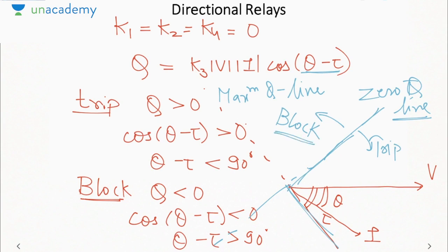Okay. So that is the phasor diagram or graphical representation of the operation of directional relay. Is it fine? So remember, there are two lines. One is the maximum torque line and the other is the 0 torque line based on the value of tau, where tau is an adjustable parameter that depends on the relay parameters during the construction.